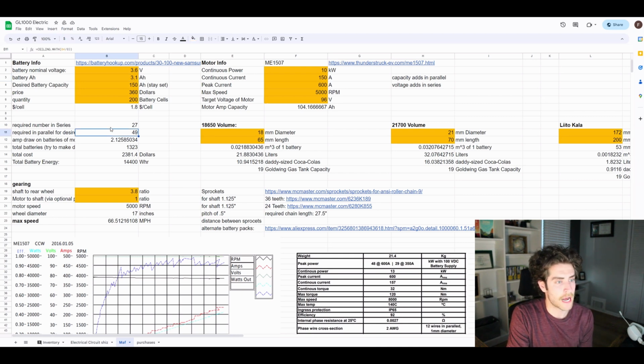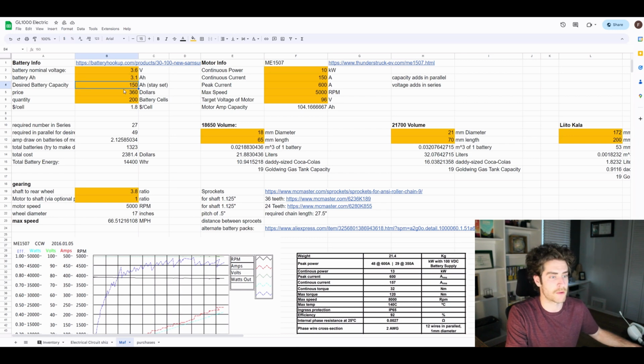To do that math, I have 3.1 amp hours, but I want a target battery pack capacity of 150. So I take 150 divided by 3.1, which gets me to 49. In both of these calculations I apply a ceiling operator because I can't have a portion of a battery. I also have other calculations to determine how much I'm paying per watt hour so I can be efficient with energy costs, but I won't cover that here, though the math is there if you want to check it.